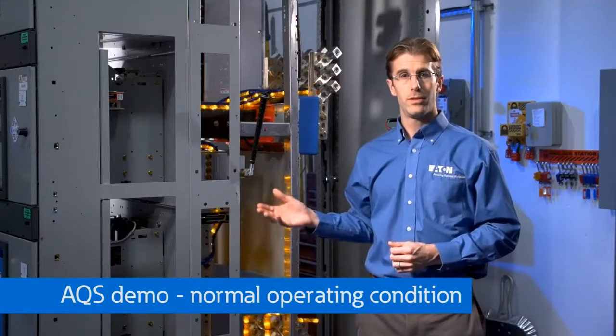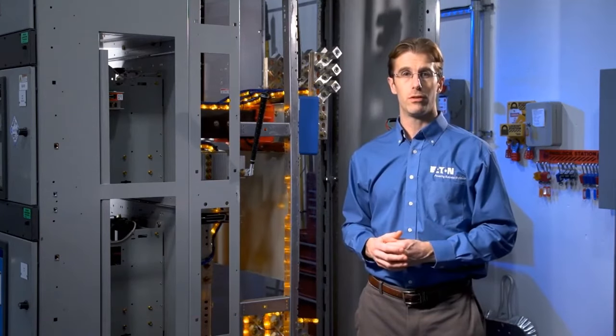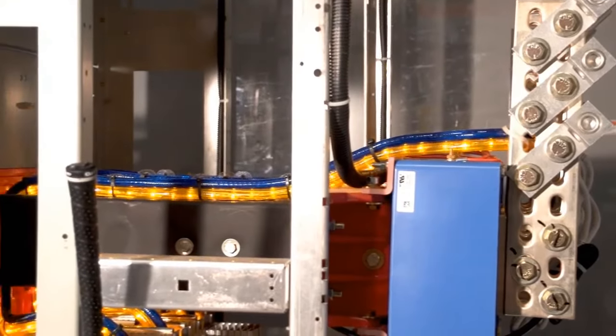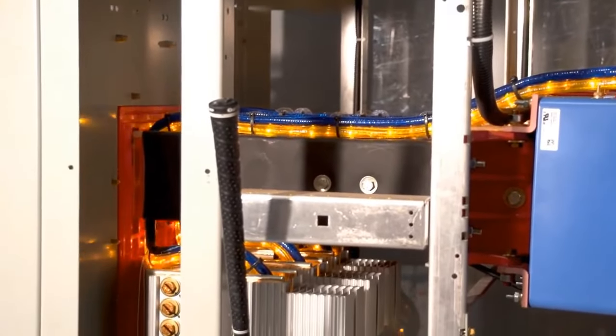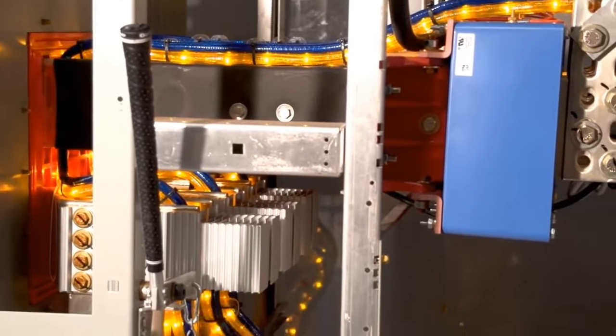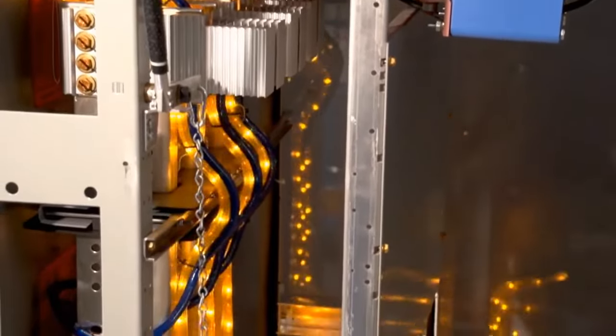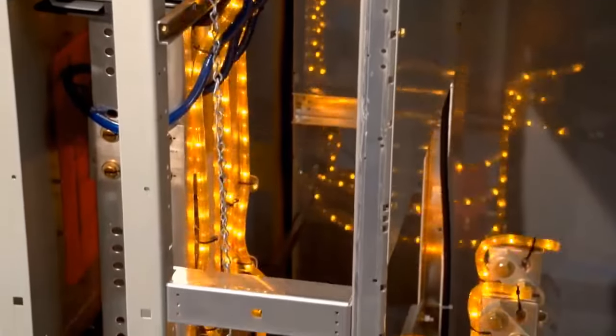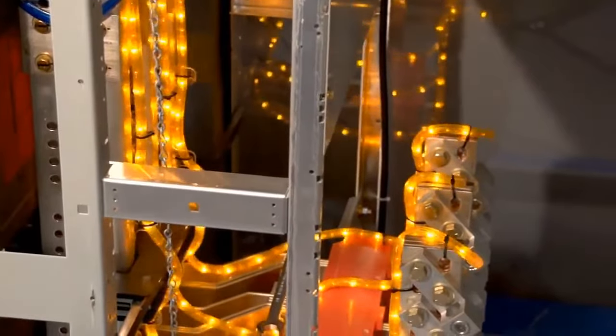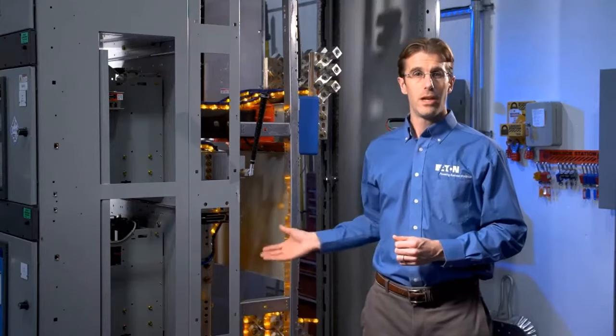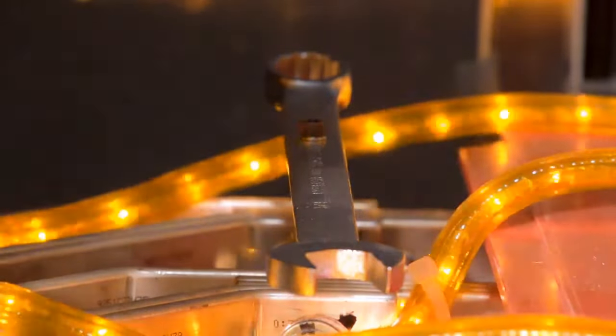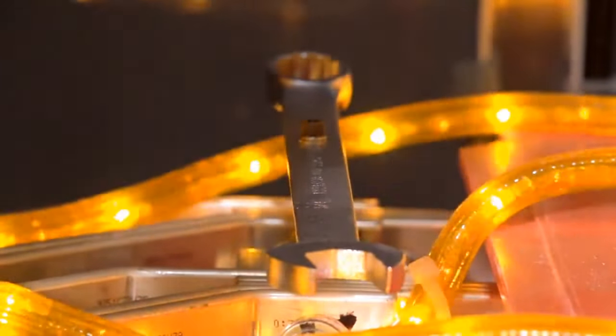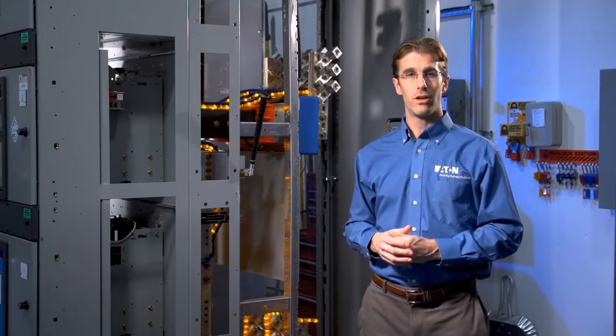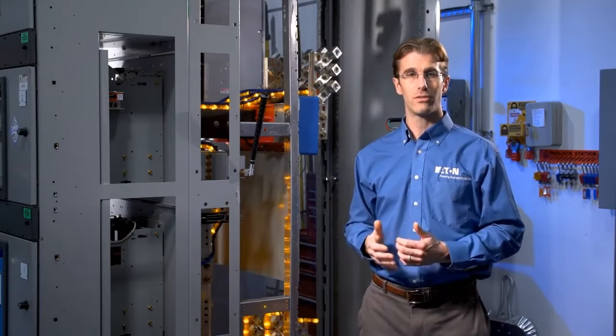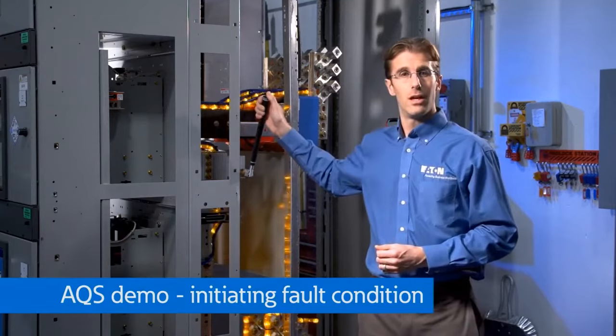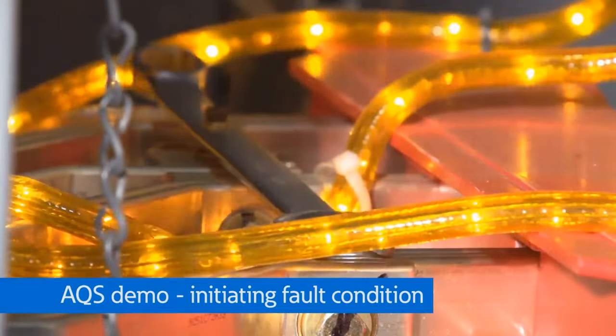For this demo, the yellow chasing rope lights show the normal flow of current in the switchgear. The current comes in through the incoming line, flows into the line side of the main low voltage power circuit breaker, out the load side, down the vertical bus, and then out into the horizontal bus, which would be distributed out to additional sections of feeder breakers. And you'll notice that it appears someone left a wrench magically levitating over that uninsulated bus bar. Let's lower that wrench onto the bus bar to create an arc flash and see what this system does when there's an arc flash inside the switchgear. I'll lower this wrench down onto the bus.